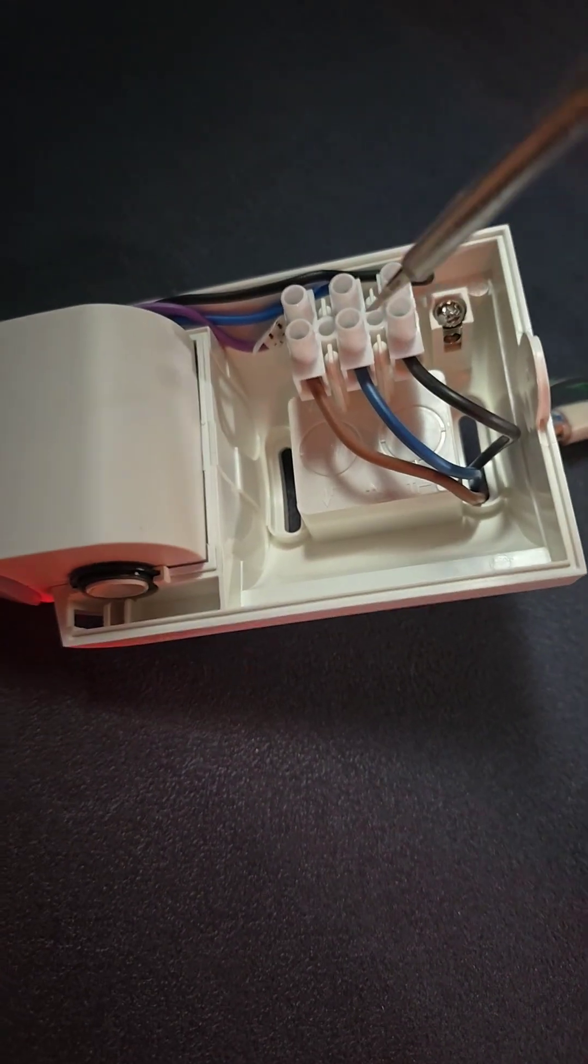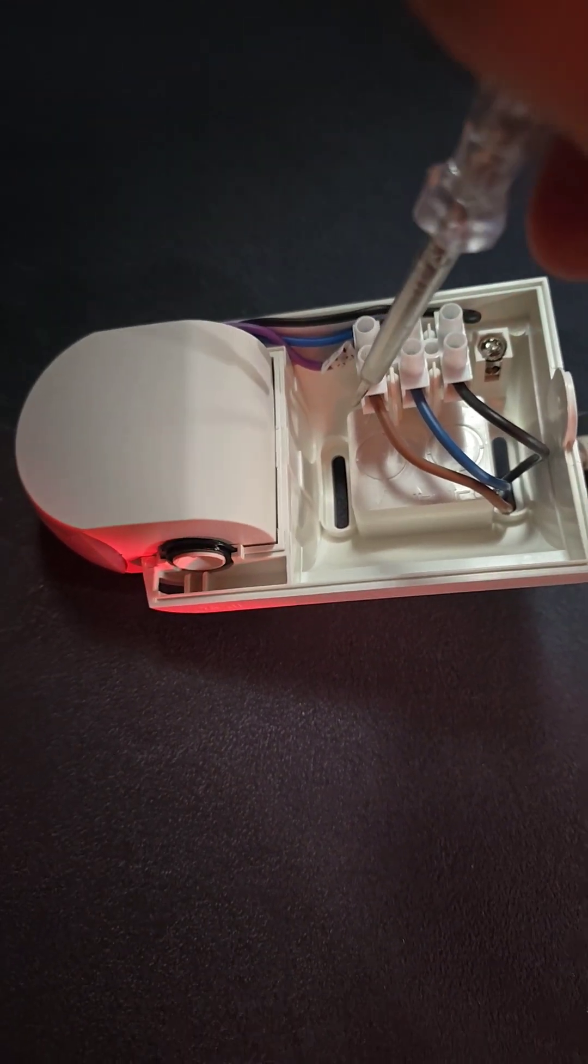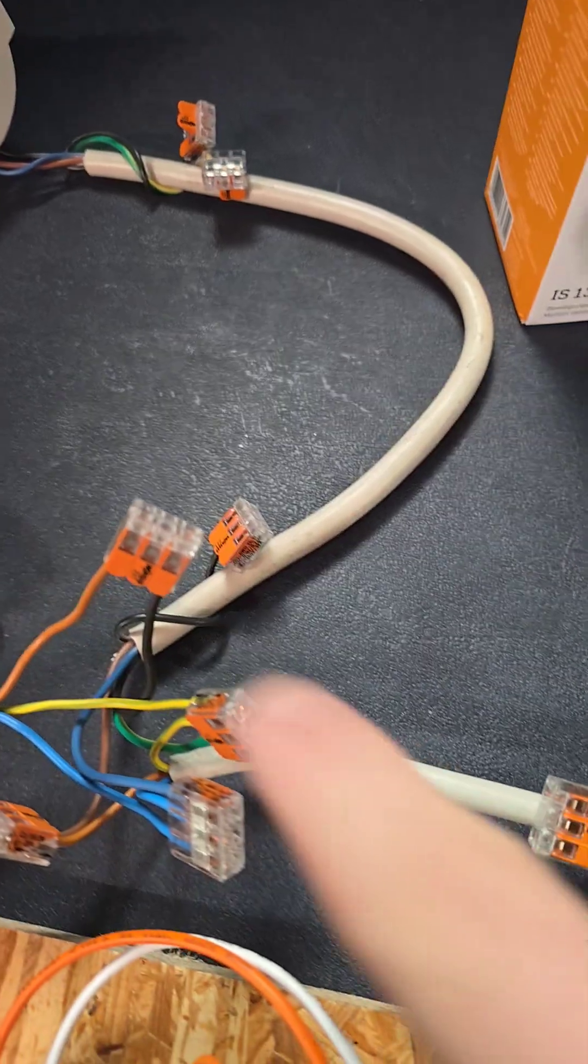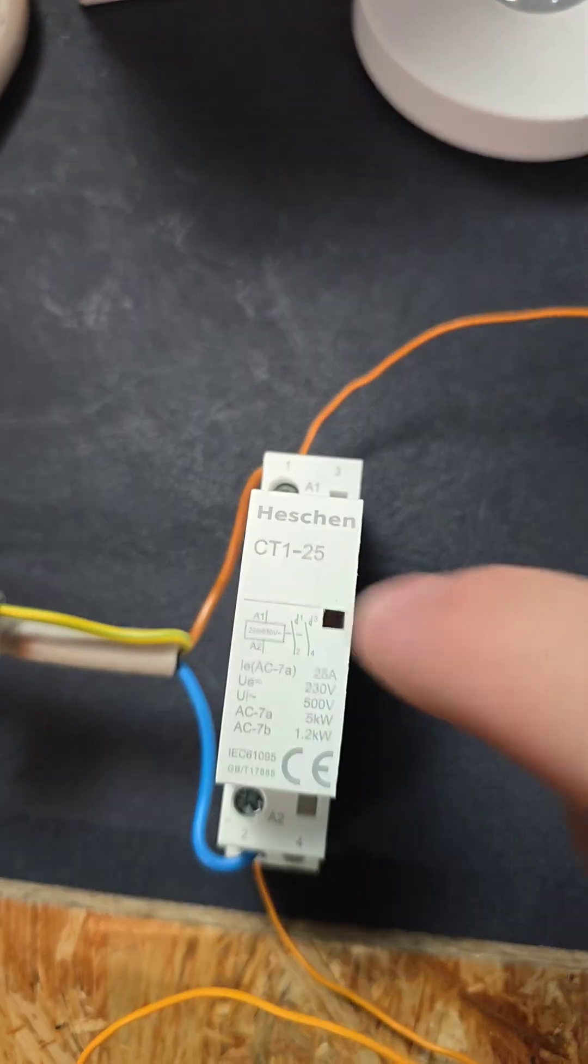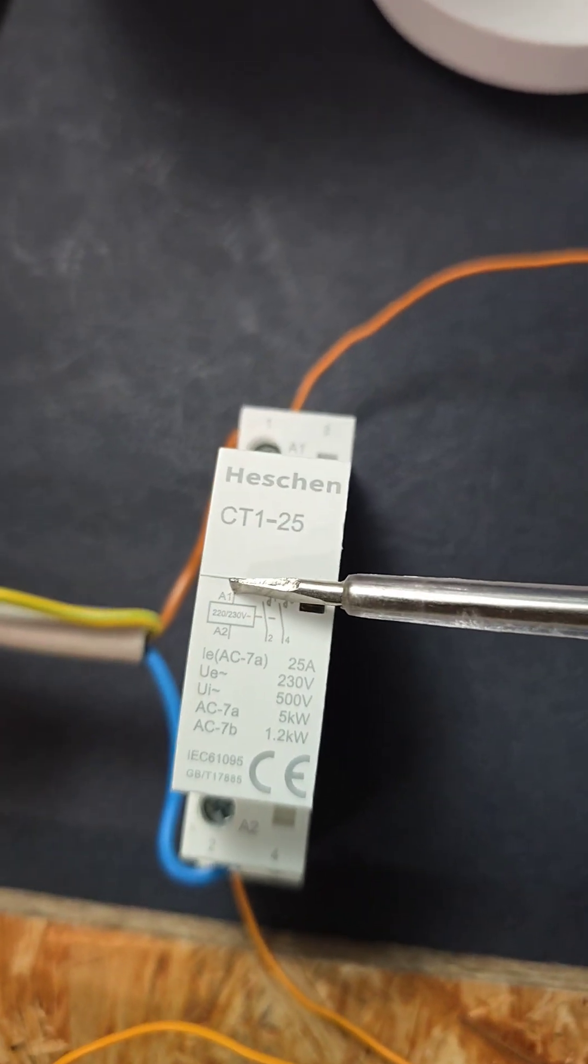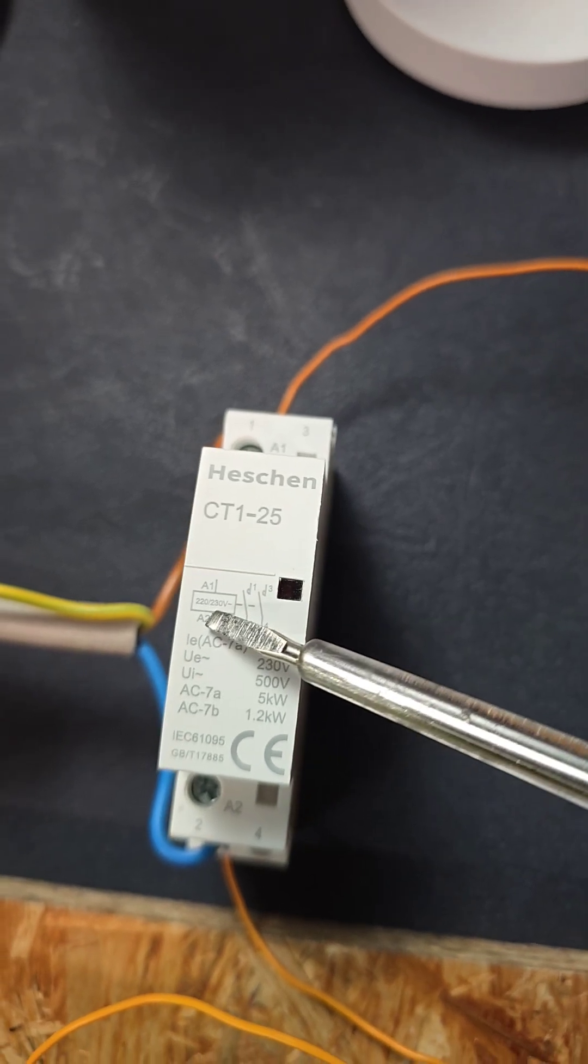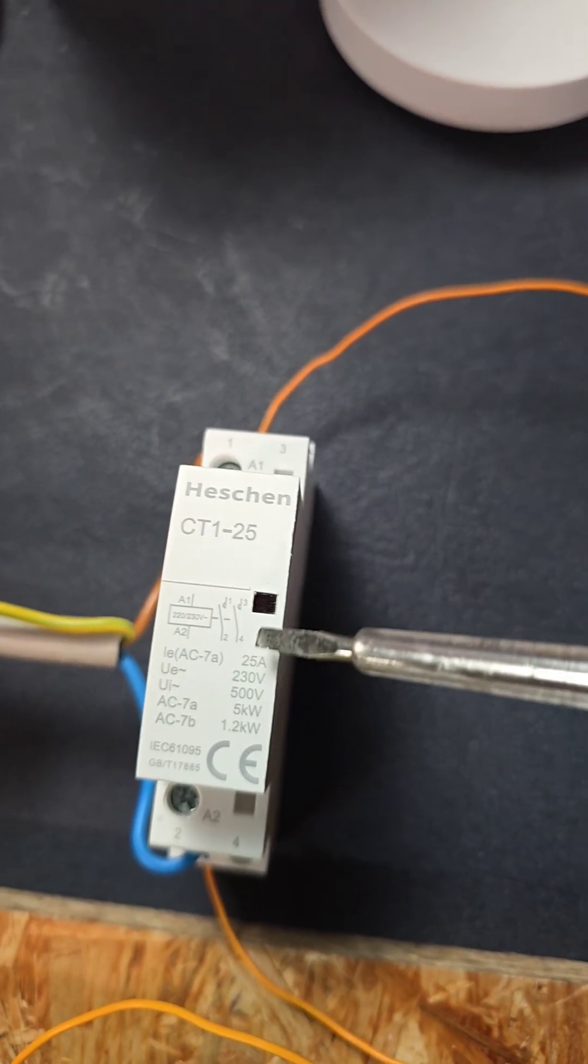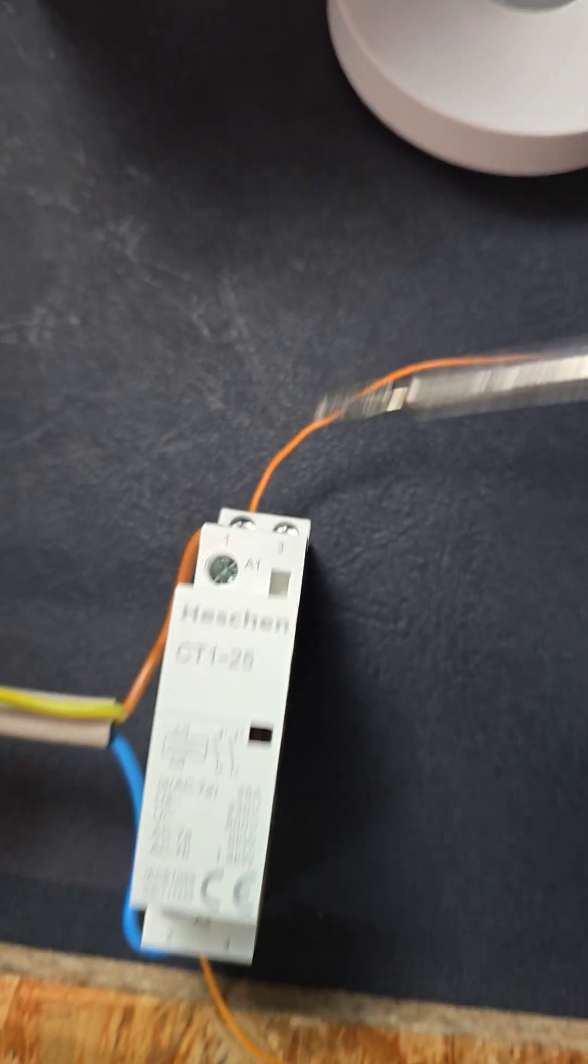I go with the permanent power to the presence sensor as usual, having the permanent and the neutral here. And if there is motion detected, 230 or 110 goes back on the brown one. This brown one is then going here to this so-called coupling relay. And what this one does is if there is power from A1 and A2 here, it's a 220-230 volt version. There are other ones as well. Then there is a connection between number one and number two.